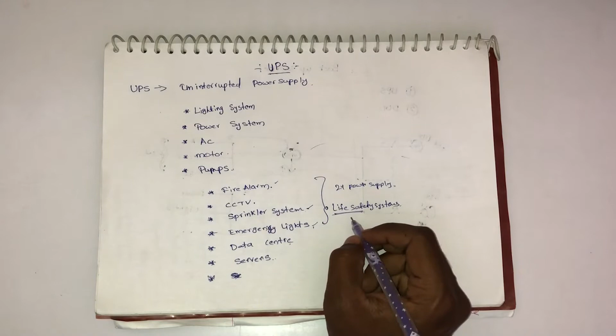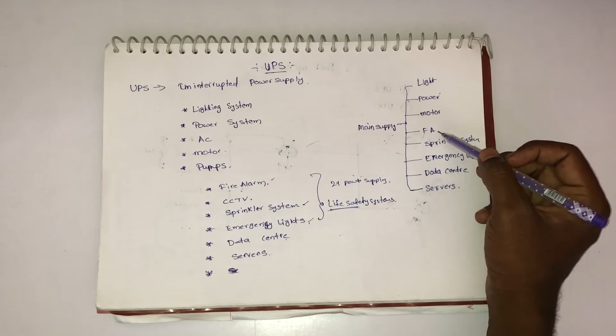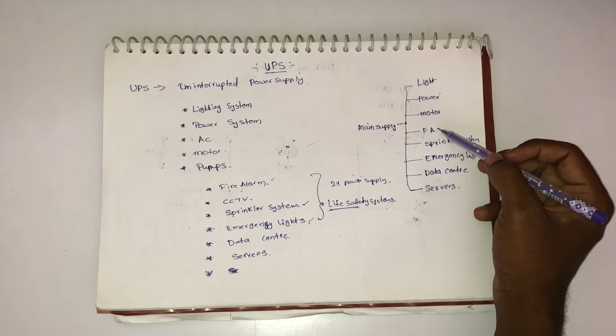The meaning of life safety system means it can control the fire and it can save lives. In the normal situation, the main supplies the power to all these systems, including life safety and this lighting, power, and data center server. But when the main supply is off, all these systems, including lighting, power, motor, and this data center, fire alarm, everything should be shut down. In that situation, suppose the fire happened, you may not be able to control it because your fire alarm system is already shut down. And also the data center and server will be shut down.